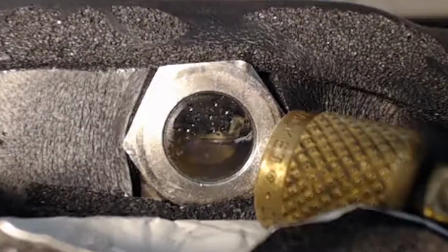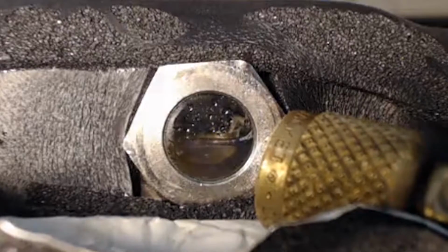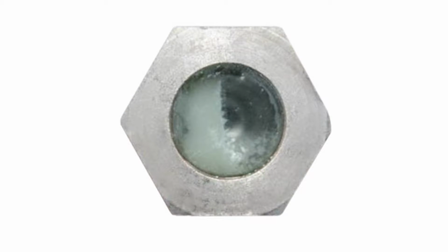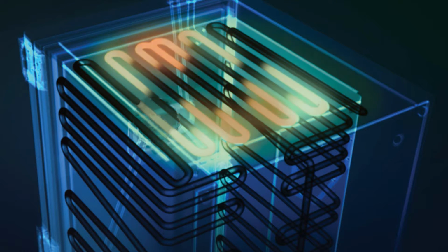Did you know that a primary cause of freezer failure in an ultra-low is too much oil in the refrigeration system? Compressors require oil to function properly, but oil that sits idle in a cold environment will form clogs that prevent the refrigerant from moving through the system. This phenomenon is called oil logging. These clogs result in freezer warm-ups because the refrigerant can't move through the system to cool.